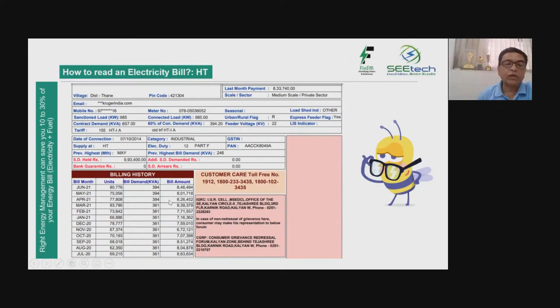So you see that this fixed charge is unnecessarily high, and now look at the actual consumption - it's only 245, 246. Whereas they are paying for 60% of the contract demand, which is 394. The power factor is all right here.